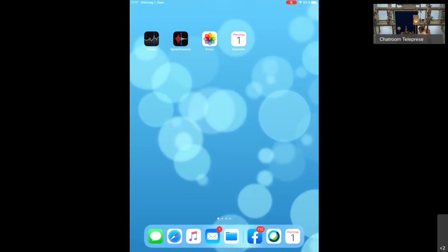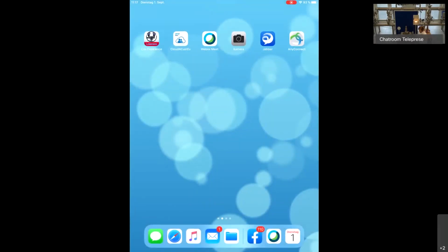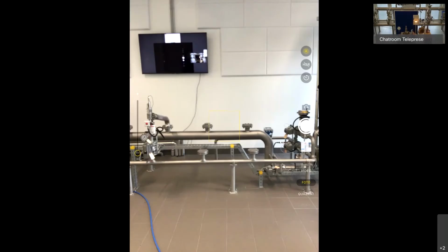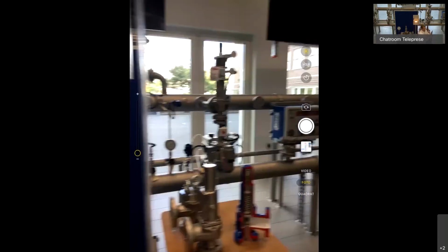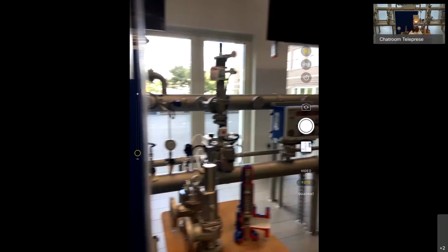I opened my camera, and now you see I'm live in the LESER chat room. Behind me stands my team, Iris Nachtigall and Philip. Now we're counting the bubbles. We have to wait. There is a first bubble, and now we count for 10 seconds according to LESER global standards.